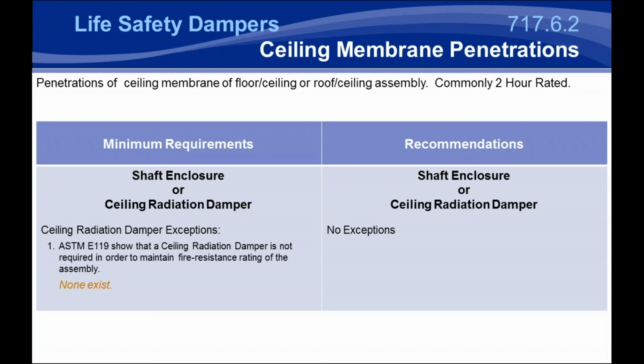Typically those are going to be some of your older construction methods, and because of that, more generic dampers were used. It was before UL realized they needed specific models and specific protections for floor ceiling and roof ceiling assemblies. Basically, when you look at those types of assemblies, it's just going to specify ductwork and a very loose damper construction, and basically any damper that's certified to UL 555C can be used there.